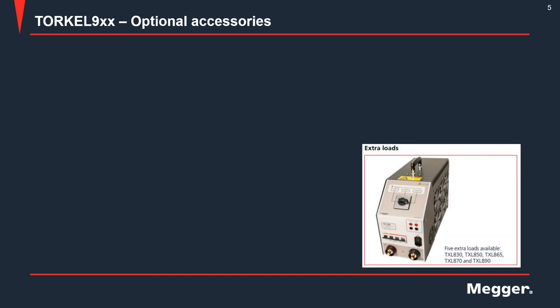The optional accessories for the TORKEL include extra load units, or TXL units, which are available in different models. These extra load units are connected in parallel with the TORKEL to expand the current capability. If you want to run a discharge test at a current which the TORKEL cannot draw by itself, you would connect one or multiple extra load units in parallel to draw the desired current. Based on the voltage rating of the battery bank and the desired test current, you would choose which TXL unit to buy or rent.